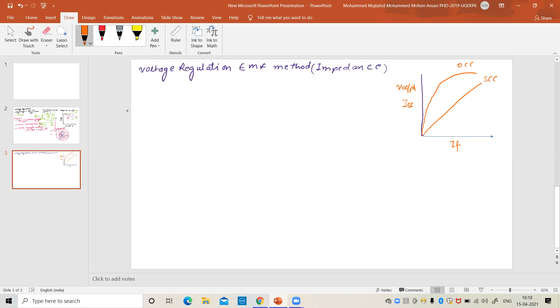From this, we already calculated the synchronous impedance ZS is equal to VOC per phase divided by ISC, the short circuit current, at IF equal to constant. We have already covered the meaning of IF constant. It means that at a particular value of the field current, we take the corresponding short circuit current and open circuit voltage. Say for example, we have taken the open circuit voltage over here, and if you go to the field current, we will find this is our short circuit current.